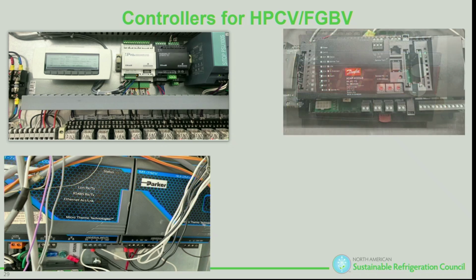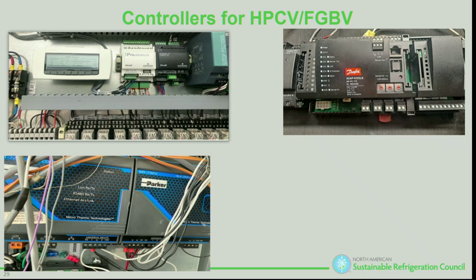But it's being replaced with the 782. The same algorithm, the same operation, the same thought process that goes into the 326A is now in the 782. I just have different pins. Now instead of coming off the 326A with my flash gas bypass valve on pins 20, 21, 22, 23, and 24, I have to go to the 208C board. Instead of coming off pins 5 and 6 on the 326A, now, this is nutty, I don't know if you guys can handle this, I actually have to look at the wiring diagram and see that it's coming off the 103 board, pins 17 and 18.